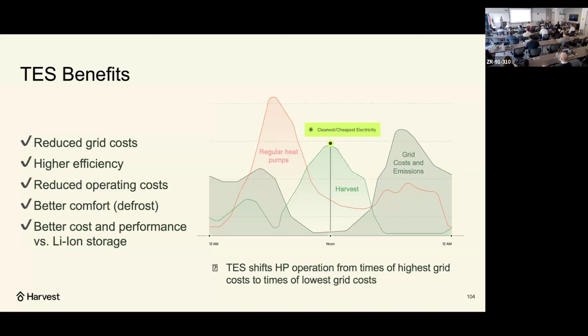We perform better at a lower cost than lithium ion. You could do the same thing with lithium ion, but it costs a lot more and it's not as efficient. The Tesla Powerwall, when new, has a 92% round trip efficiency. We have 95%, and ours doesn't degrade — it's constant over the life of the system — whereas both capacity and efficiency for lithium ion degrade over time. So better performance, efficiency, and cost.